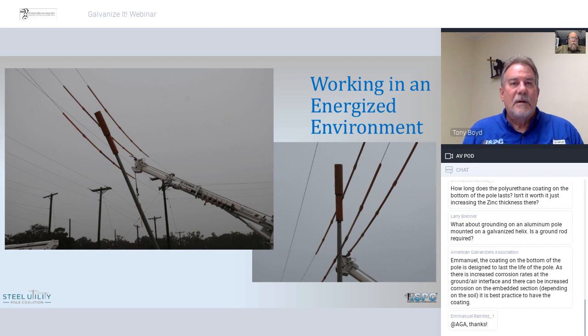If I'm picking up the pole using a digger derrick or a crane, as the butt of the pole is moving into position, it's kind of hard to put a ground on there, especially if it's a pole that has to be dropped in from above down to the ground. So we found a way to accommodate that as contractors that were setting in here, and that was by using a 2-aught ground. And on the end of the ground, we took a magnet that is available in any hardware store, a good substantial magnet. They're about 2 inches in diameter, with a steel housing on it with a hole in the center, and we stick a bolt through the hole and we bolt it on the end of a ground cable.